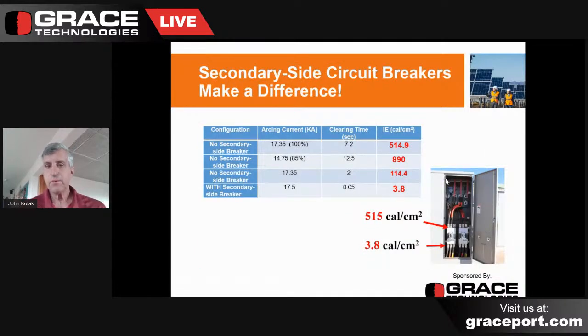Now, let's take a look at the incident energy at various points in the system here, and also at different current levels. You'll notice that in this case, the top of that breaker is fed directly from the transformer. And it is important to understand that the overcurrent protection in a pad mount transformer is on the high voltage windings, not on the low voltage windings normally. So normally when you have fusing on a transformer, it only is protecting the high side of the transformer, and we'll talk about the significance of that from an arc flash standpoint right here.